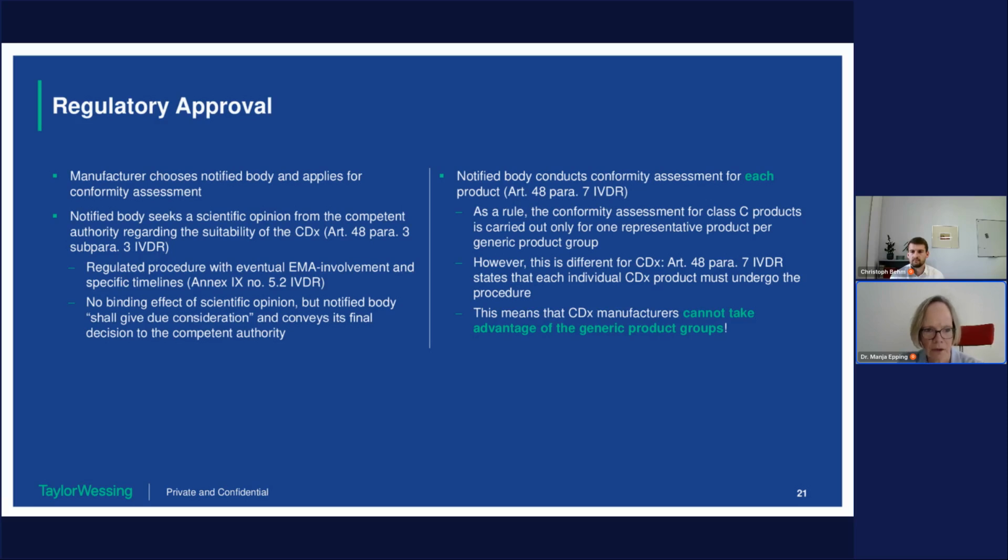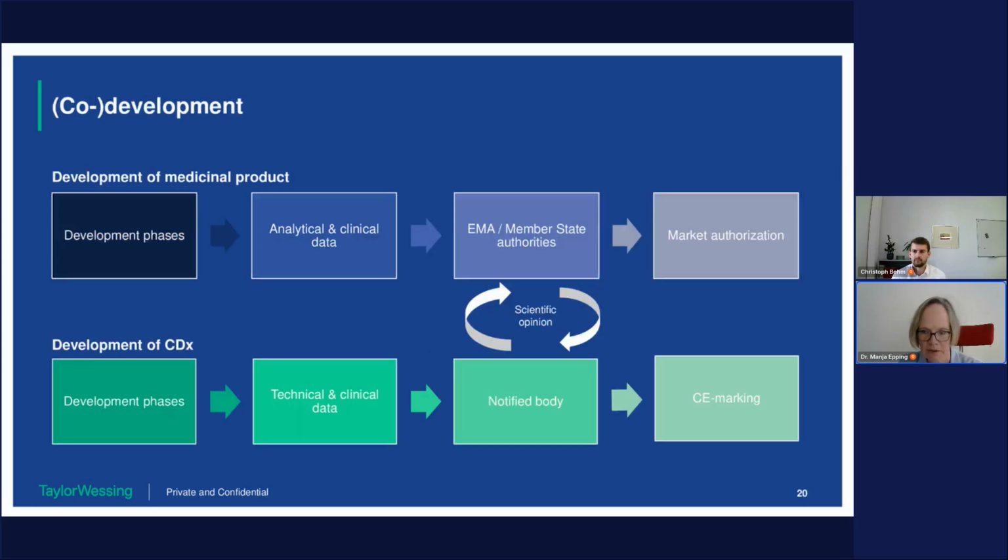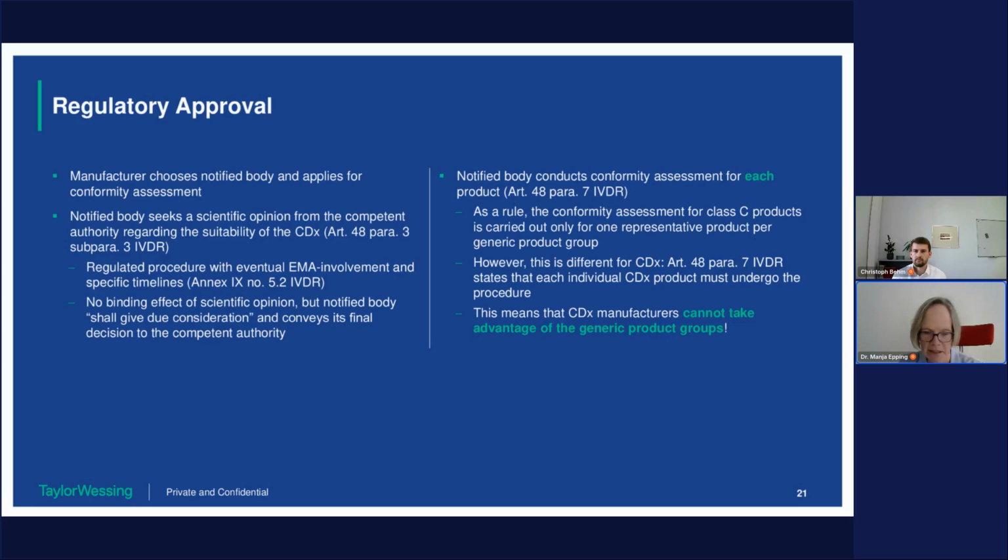So how is this link established at the regulatory stage that we just saw? I might go back to this link. How is this established? You can find the legal basis in Article 48 of the IVDR. This is a so-called consultation procedure that is mandatory. The notified body has to involve the regulatory authority, and depending on which type of regulated product, that decides which authority is involved.